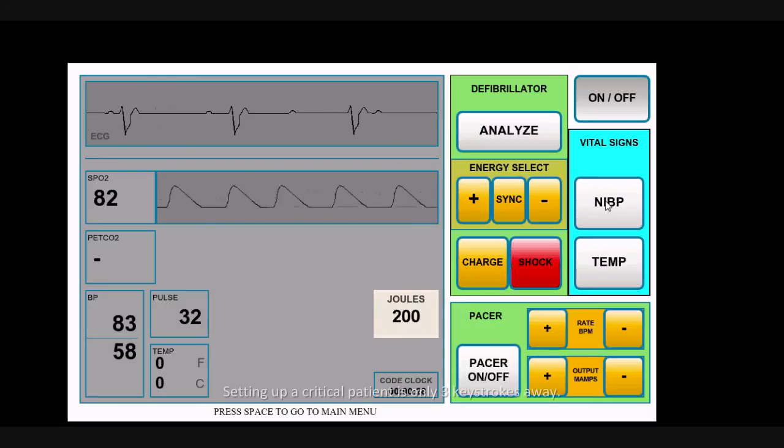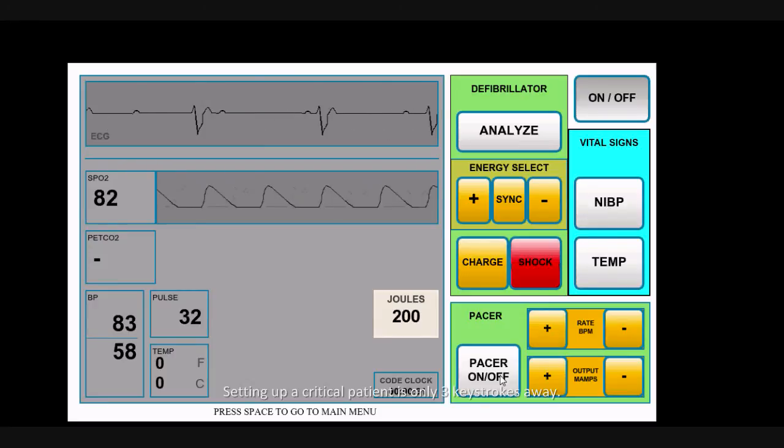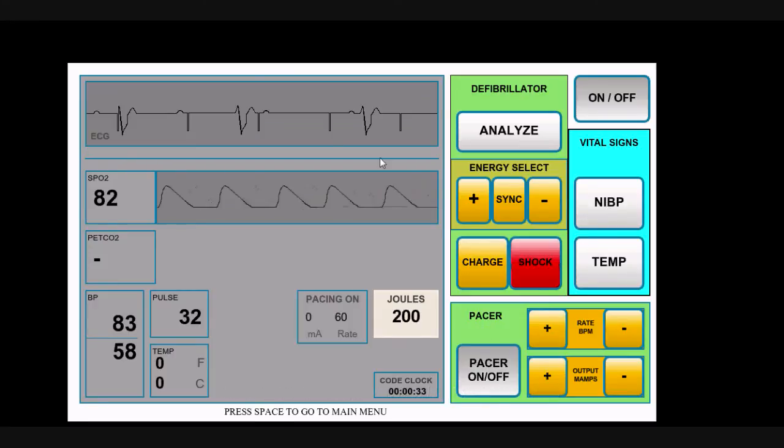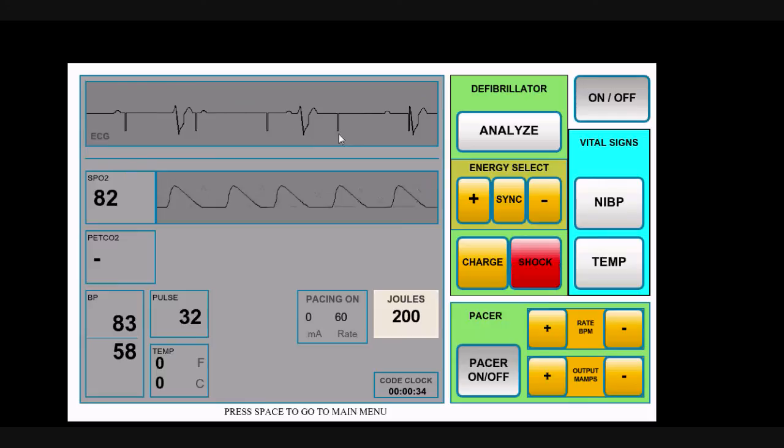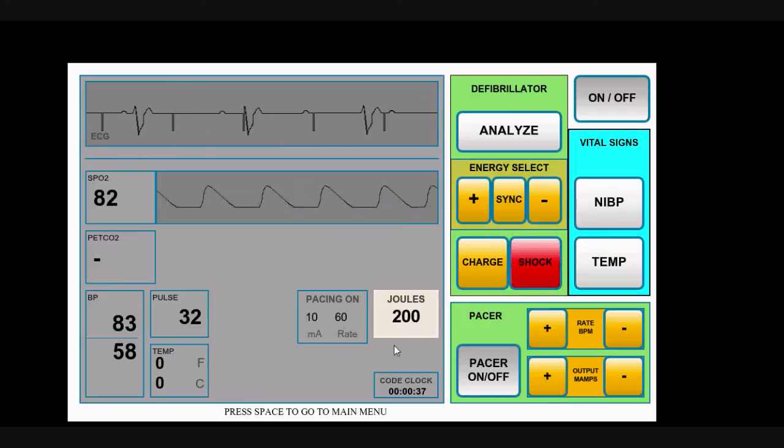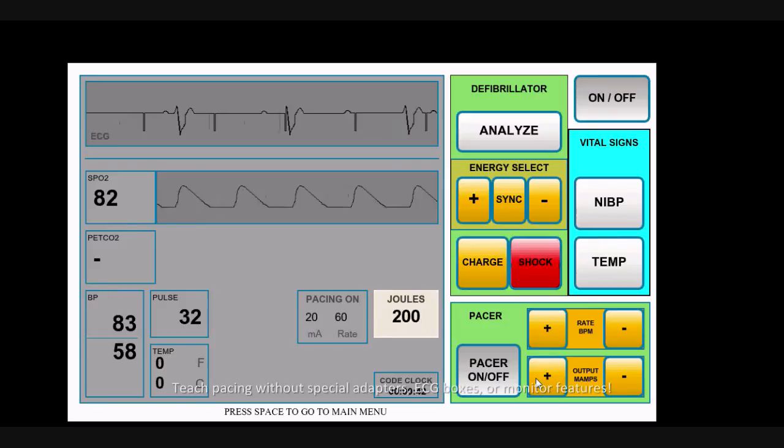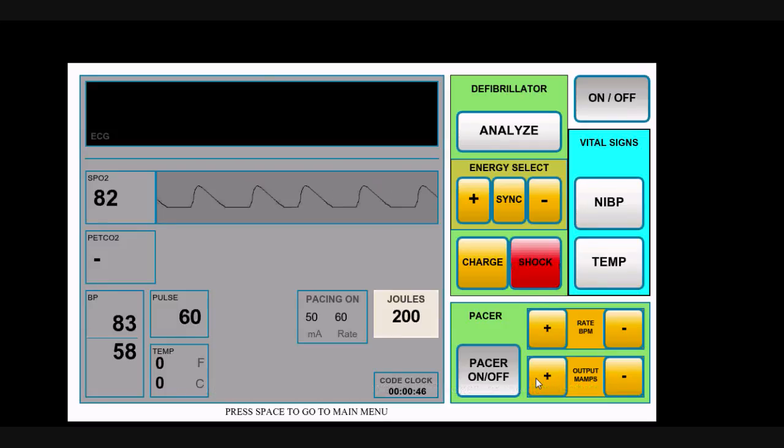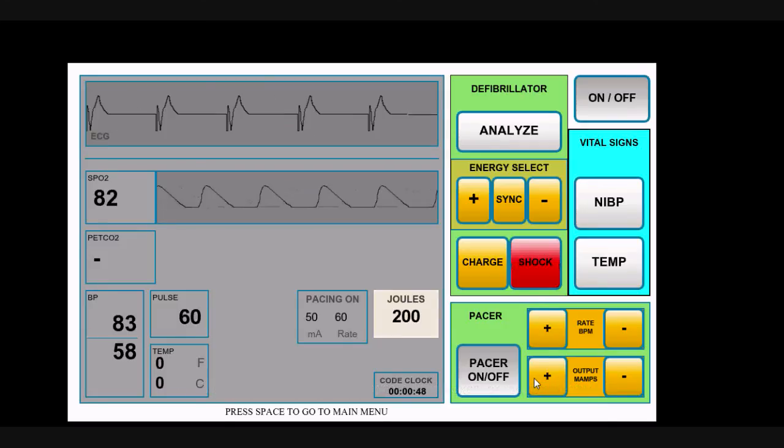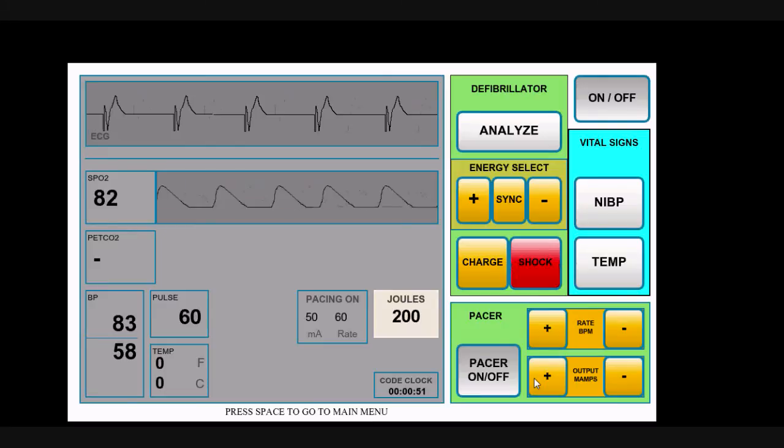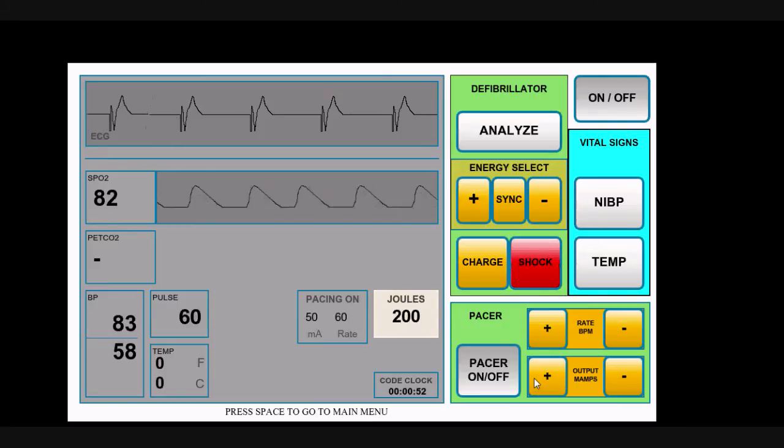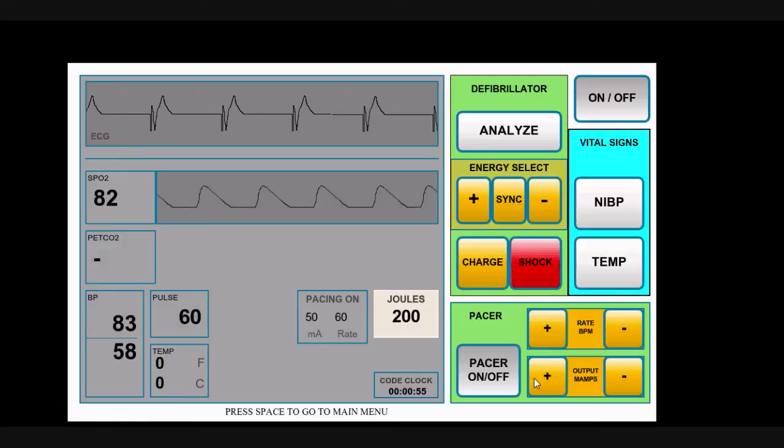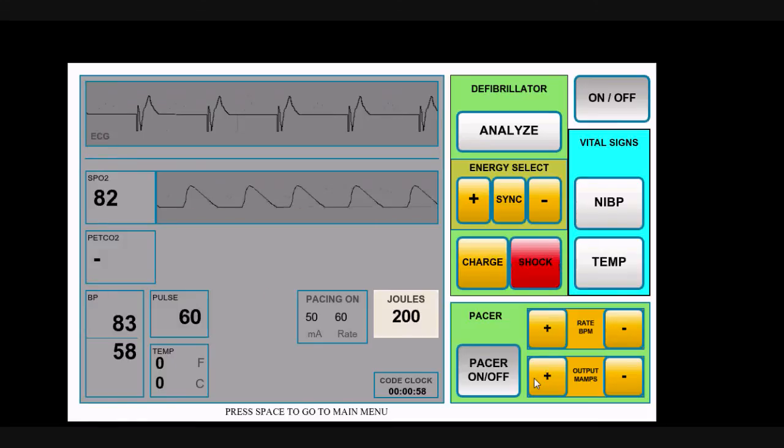Let's say they've elected to pace this patient. The product will do all of the normal pacing stuff. If you hit pacer, you'll see the pacer spikes. They need to increase the outputs in milliamps. You'll notice here the output milliamps and here the rate. As I go up, once I hit the threshold, and the thresholds are programmable using the function keys. There's three or four of them. Some of them convert at 40. Some of them convert at the default of 50. You can make it as high as 80 for a patient with lots of impedance, perhaps someone a little bit heavier. And now you see capture on the monitor.